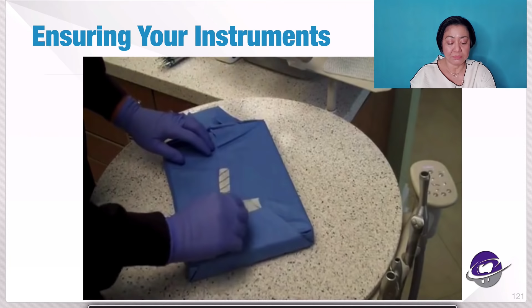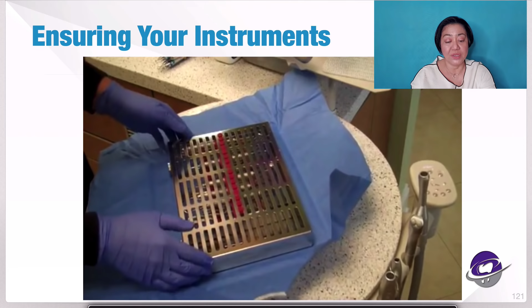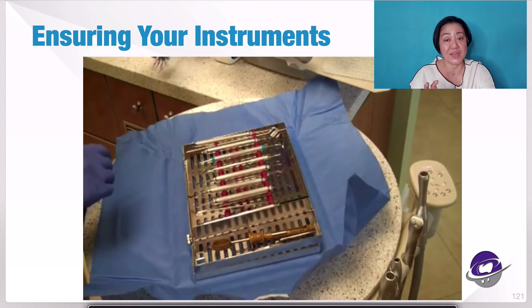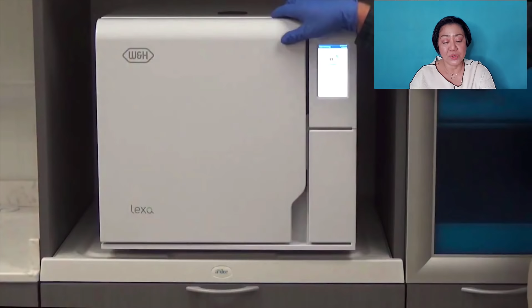So anyway, if your autoclave is class N, this is the steel cassette that you can use to autoclave your instruments. Because as I mentioned, when it comes to class N, it is better that the instruments are unwrapped. Unfortunately, if the instruments are unwrapped, once you open the autoclave, they are not sterile anymore because the air and your environment are not sterile. That's why I do suggest that you have a UV light storage area, like this one, a UV storage place, which can help with at least whatever airborne microorganisms or pathogens exist in the air. Hopefully that's not COVID-19.